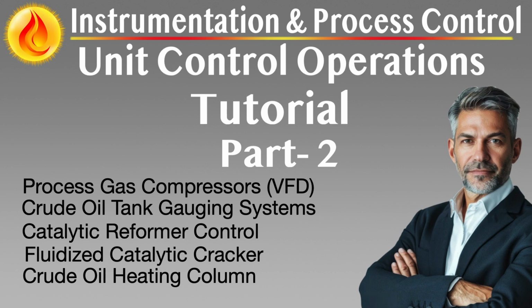Safety and reliability in reformers are managed through tight control of pressure relief systems, furnace interlocks, and reactor monitoring. Safety instrumented systems, SIS, are employed to detect overtemperature, pressure excursions, or loss of hydrogen flow, initiating staged shutdowns or transition to safe operating modes. Alarm rationalization and high-integrity operator interfaces are essential due to the high temperatures and flammable materials involved. Many modern units integrate virtual operator assistants or digital SOPs that guide response actions during startup, transitions, or emergencies.